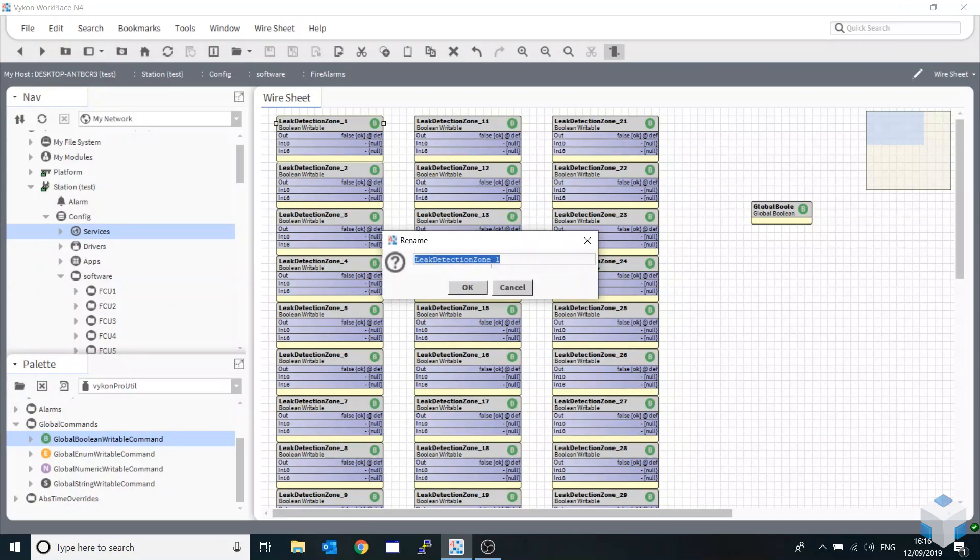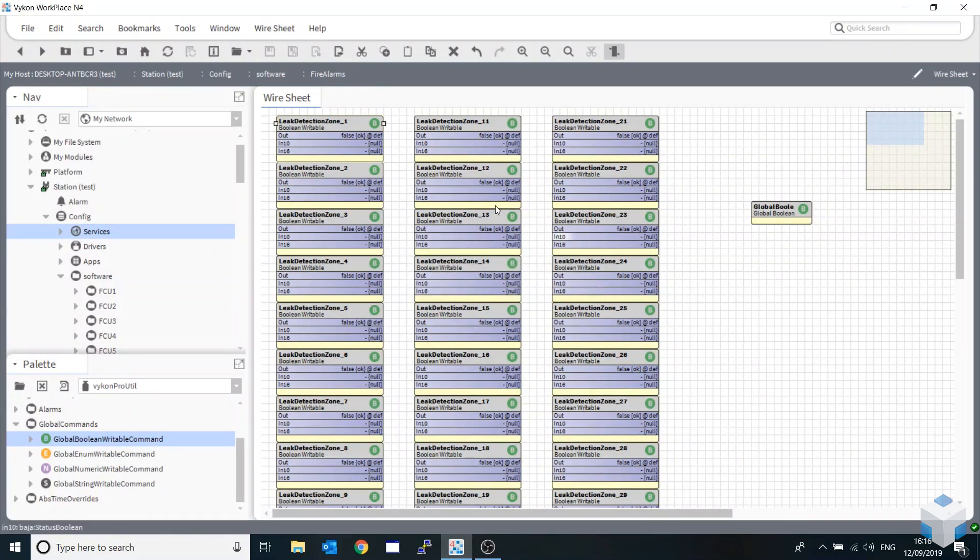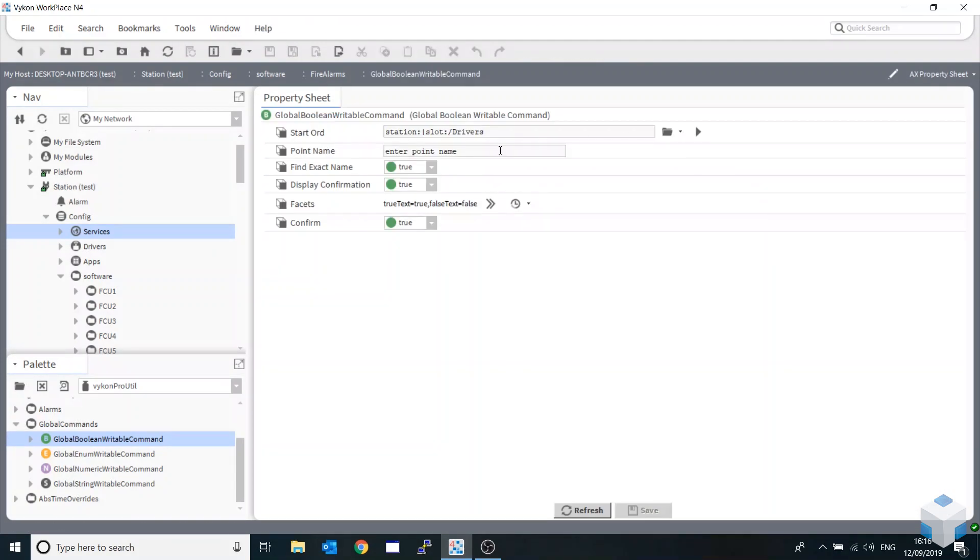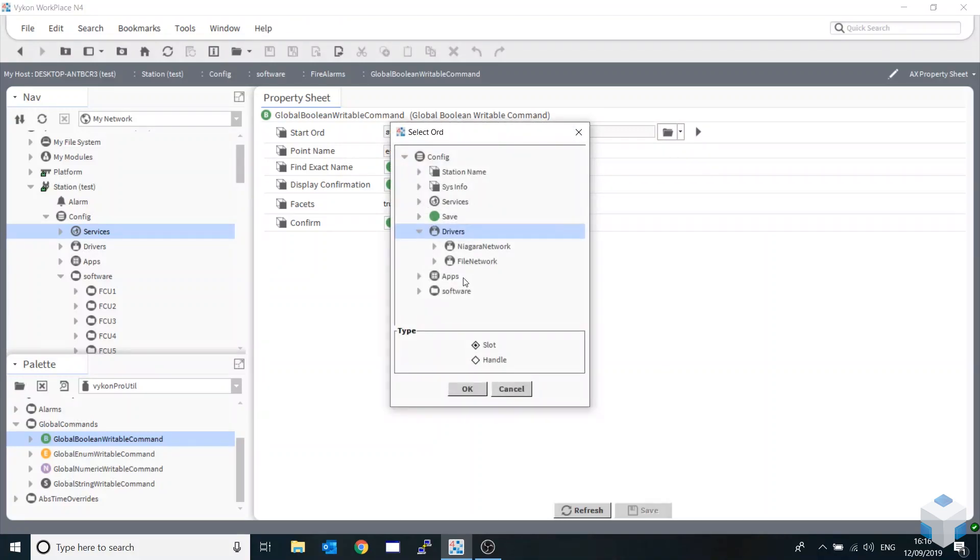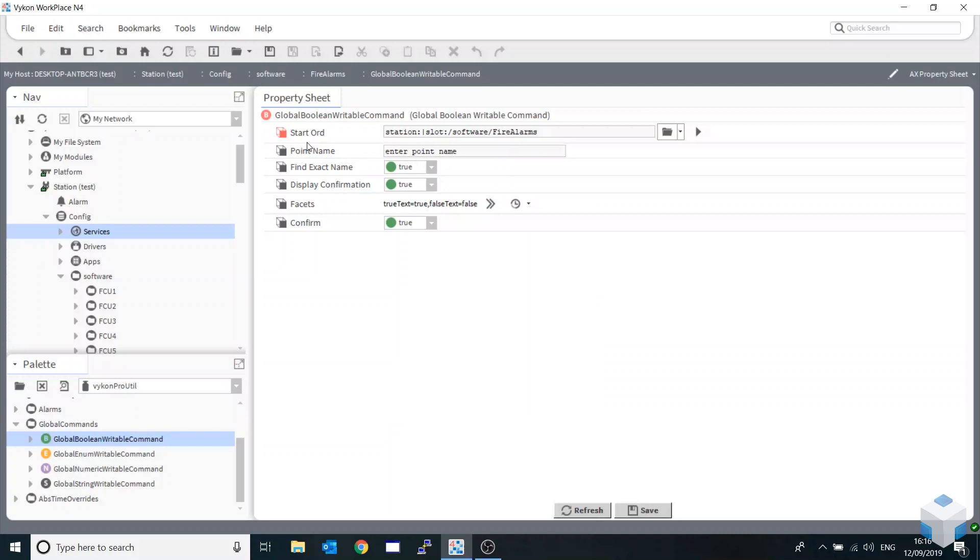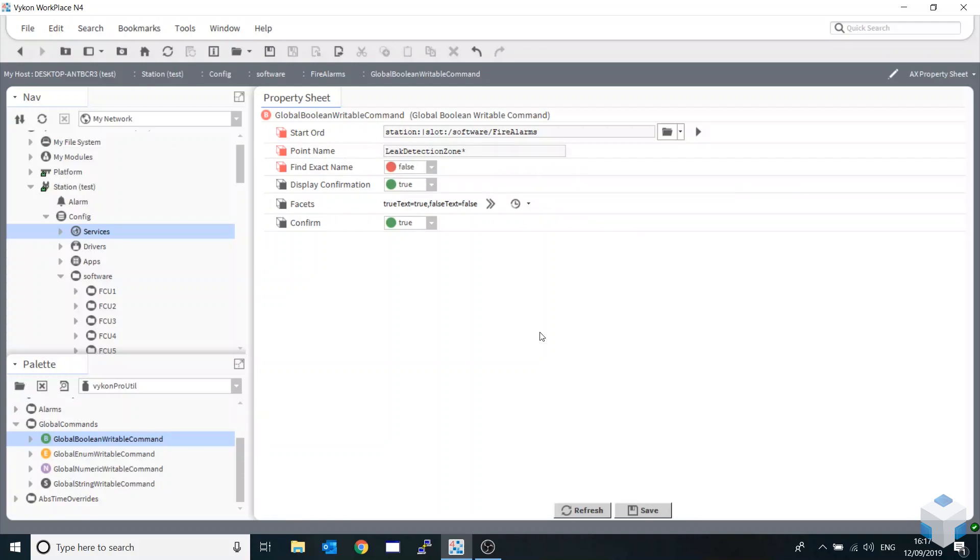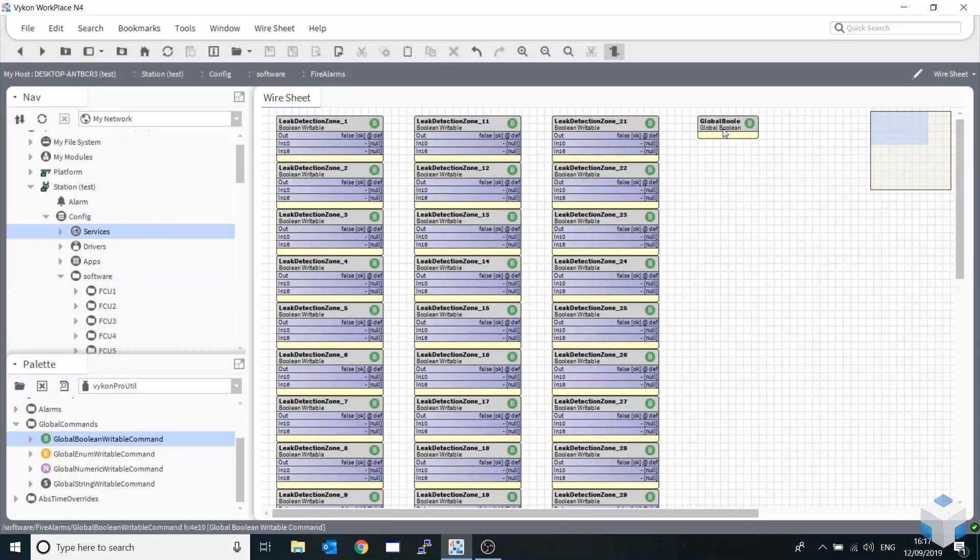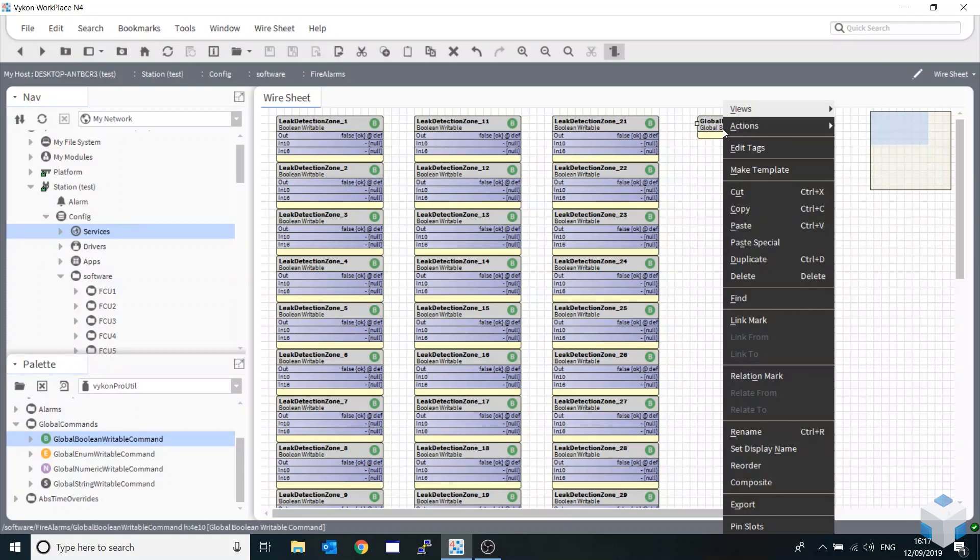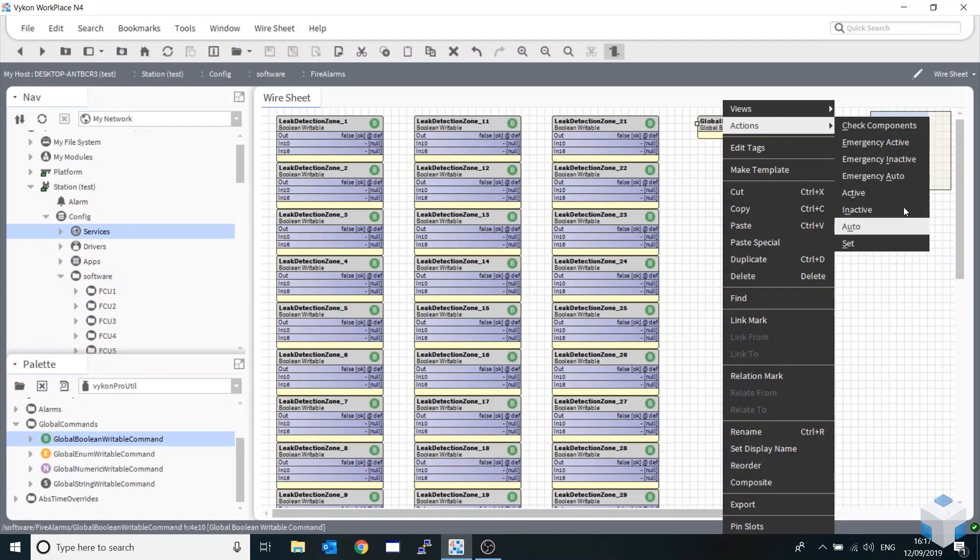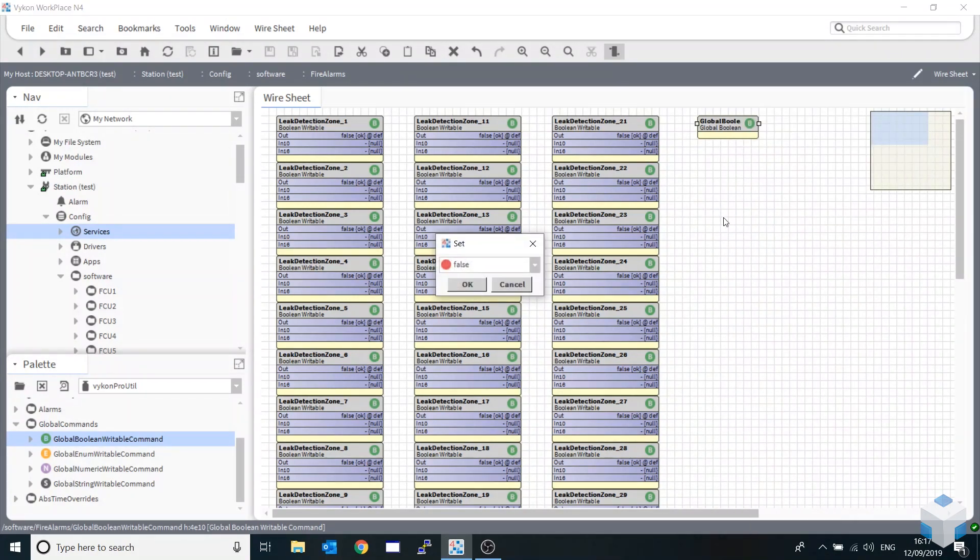After the underscore the naming convention changes, so we can drill down and point this at our folder. Enter the point name using a wildcard. I'll be using an asterisk because I want to do this on mass. Find the exact name, I'll be setting that to false, and I'll be asking it to display confirmation. I'll hit save and come back into the graphic wire sheet. I'm going to right click, actions, and set.